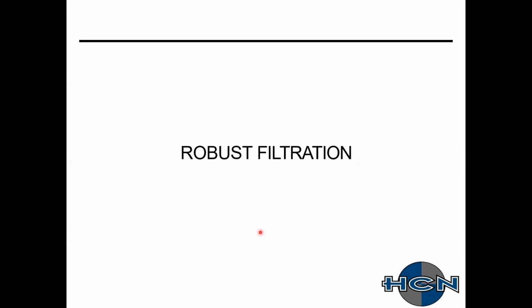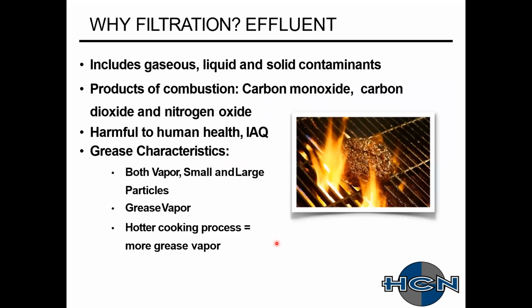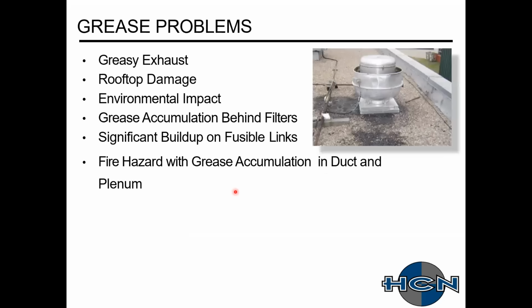So going into the next thing, filtration. Trying to capture as much as we can at the source is the easiest way to go about this. There's a few different research projects that went over this. The big thing here is we want to capture as much as we can at the source, so it's reducing the grease that's up on the hood or in the duct itself, reducing it on the roofs, and on the fusible links for the fire suppression systems, because typically those would clog up and wouldn't work.